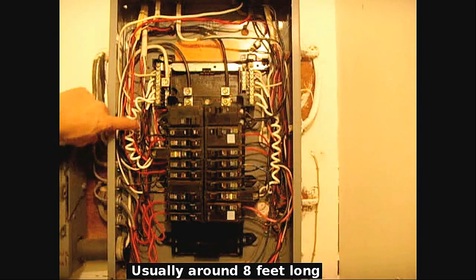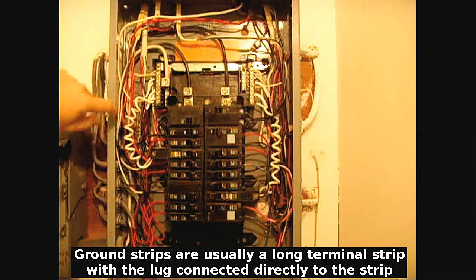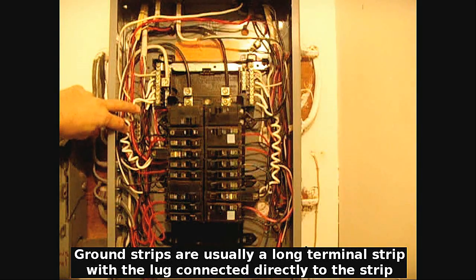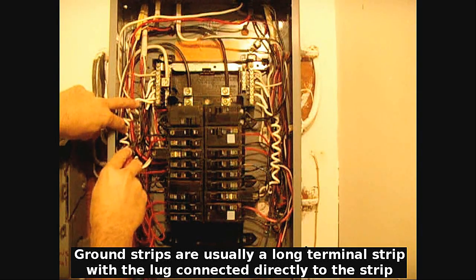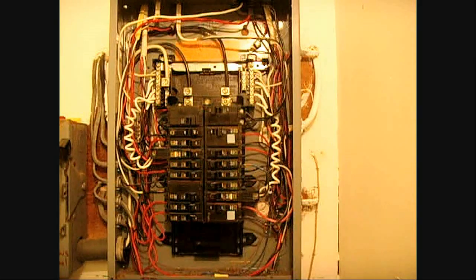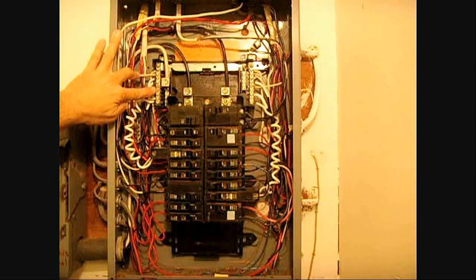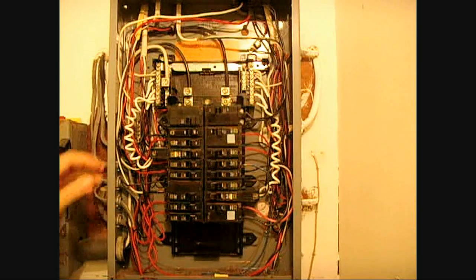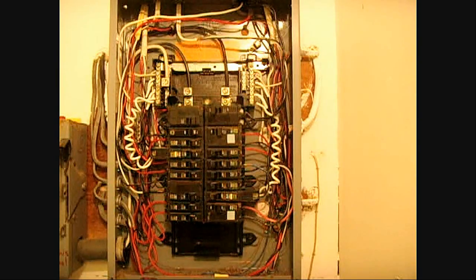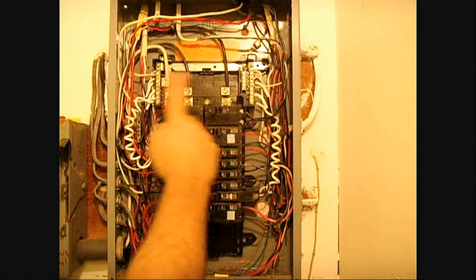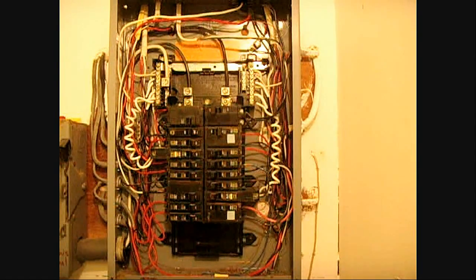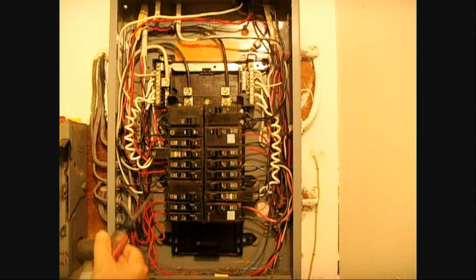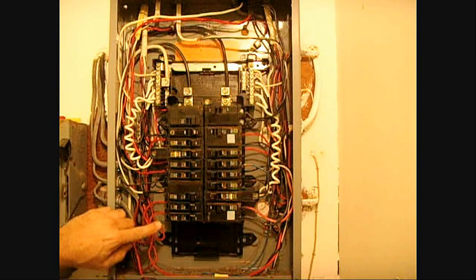You would have your separate ground bars, which you can see right here. So all of your bare wires and your green wires should all be connected to these bars here. There's one on both sides. And then all your white wires will be connected to the neutral bar. You want to make sure that's properly done. Now for code reasons, and it does vary depending on local building codes, they do not like to see splices performed inside your breaker panel. You also want to make sure that every single screw on every breaker has only one wire per screw.